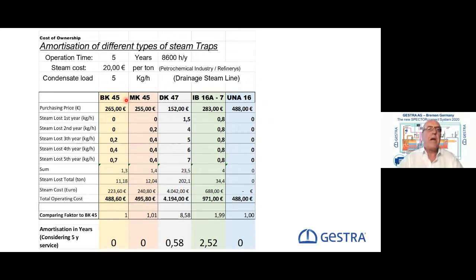We can use the bimetallic, the capsule type, the thermodynamic type, the inverted bucket type, or the ball float steam trap. These are the purchasing prices. Here is listed the steam loss over the years. Thermostatic, bimetallic: more or less zero in the first 5 years. The same with the capsule type. The increase of steam loss with the thermodynamic steam trap is a lot. I put the numbers in here, and here we have the constant steam loss of the venting orifice of the inverted bucket steam trap, and we can say that the ball float steam trap under normal conditions has no steam loss.